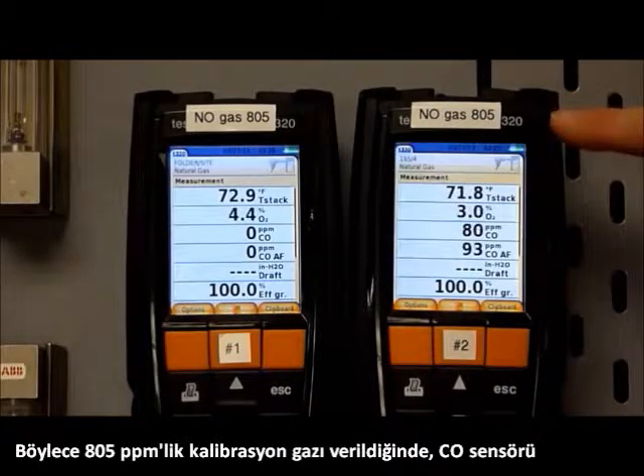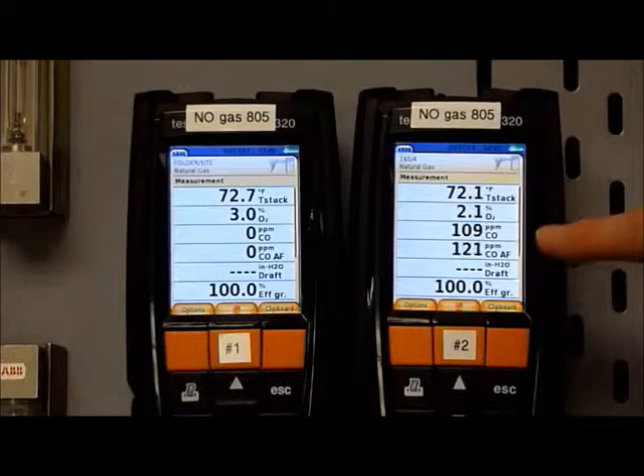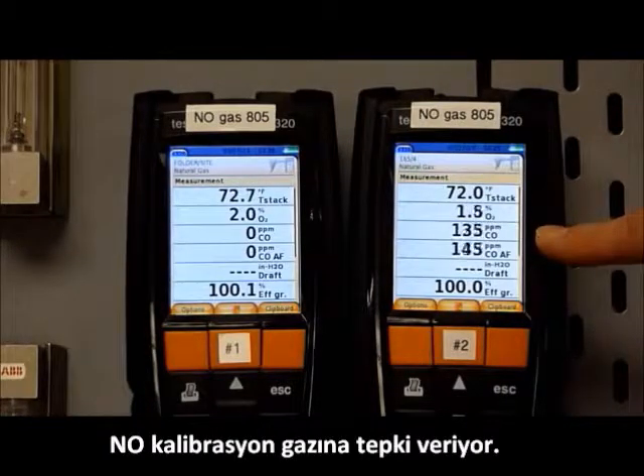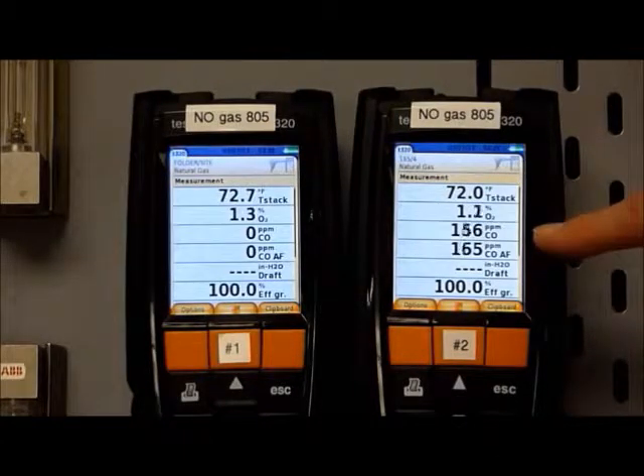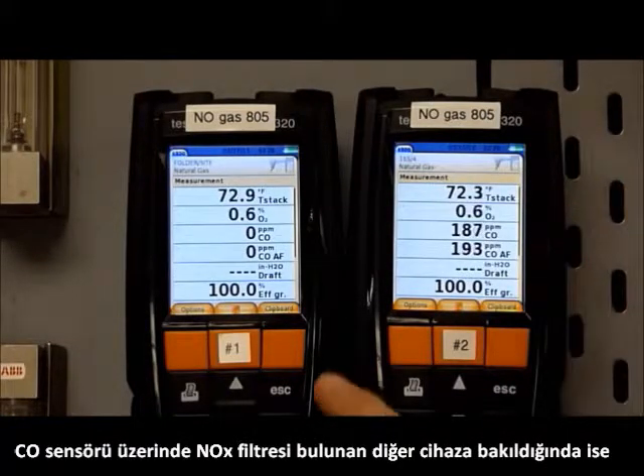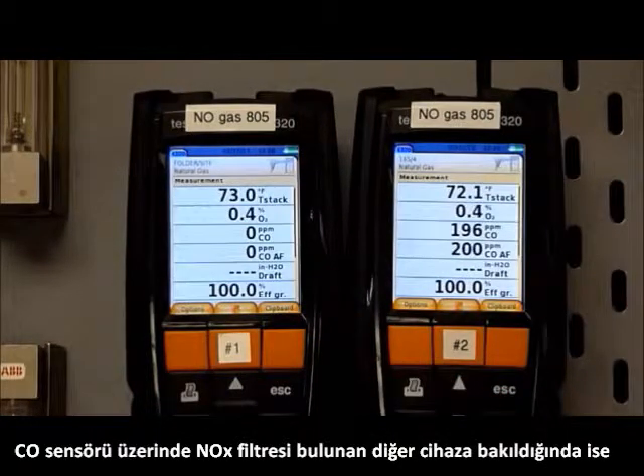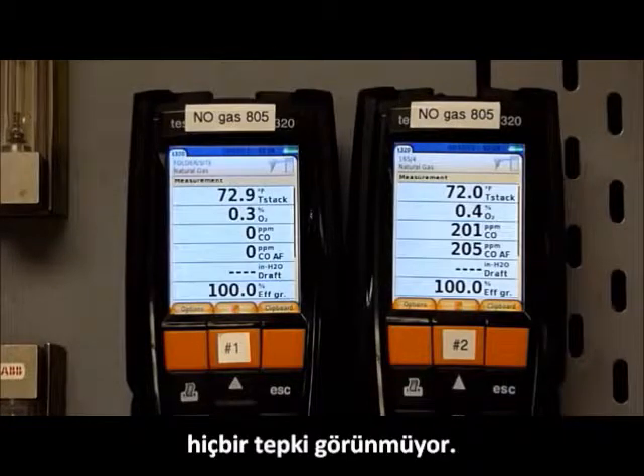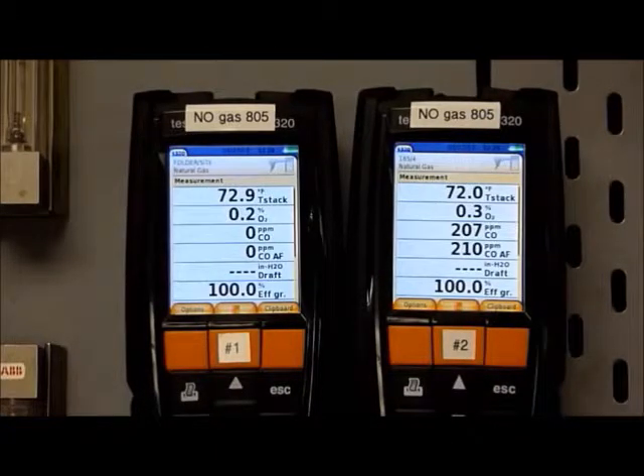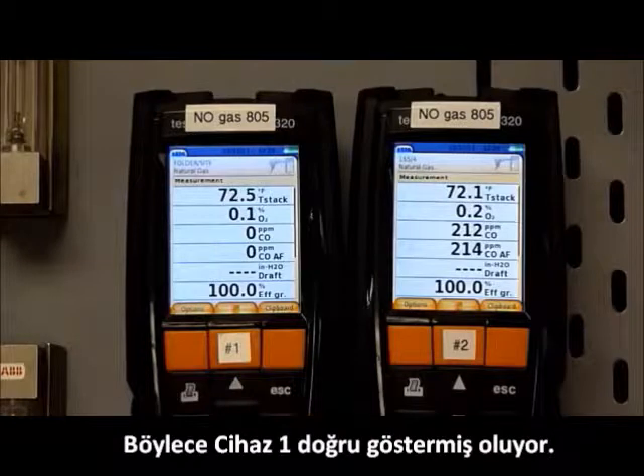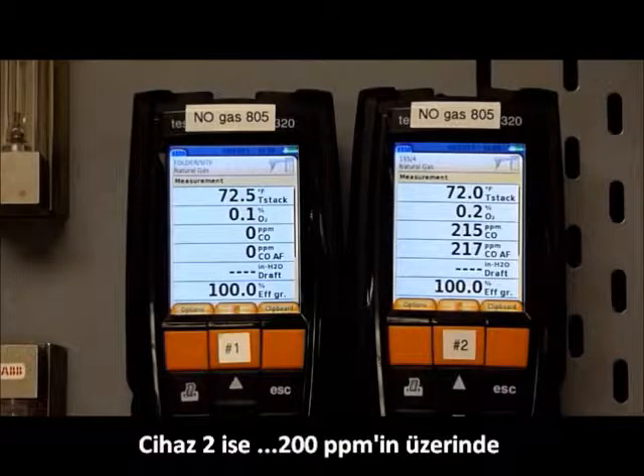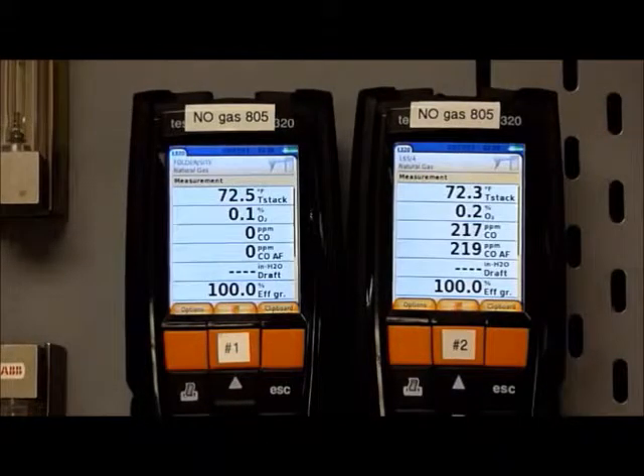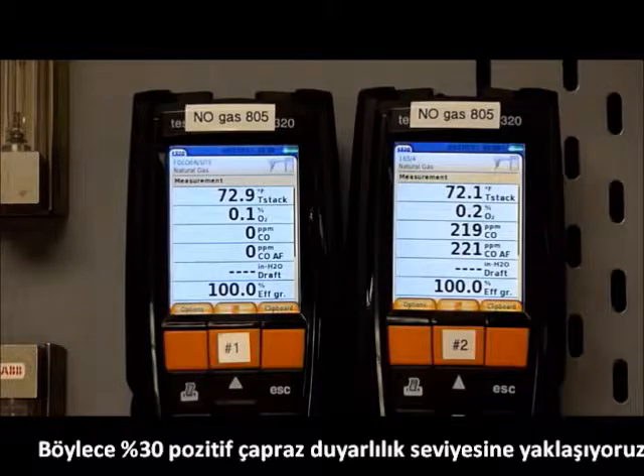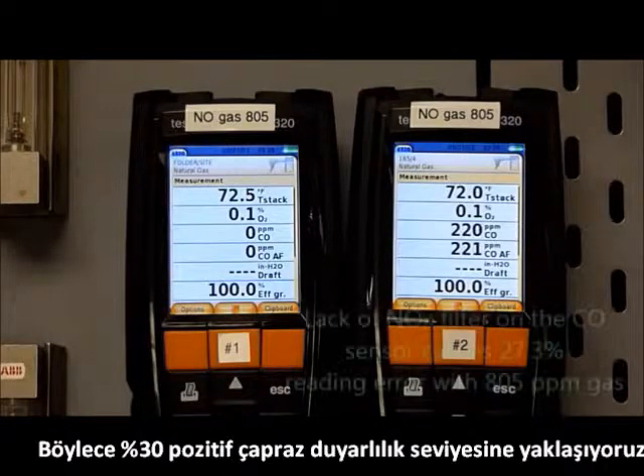So on an 800 ppm cal gas, the CO sensor is reacting to the NO cal gas, as on the other analyzer, the CO sensor with the NOx filter has no reaction at all. So analyzer 1 is measuring correctly. Analyzer 2, we're over 200 ppm, so we're approaching that 30% positive cross sensitivity.